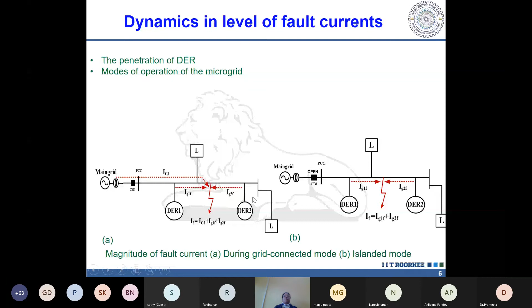So the takeaway is that with the penetration of renewable sources and with grid connected or islanded mode of operation, both the pre-fault and fault current magnitudes are modulated and changed. This is a very first important issue of smart grid networks with renewable sources, grids, and storage devices. Moving ahead, the second issue is the bidirectional fault current - the first issue was magnitude change, now what about direction?